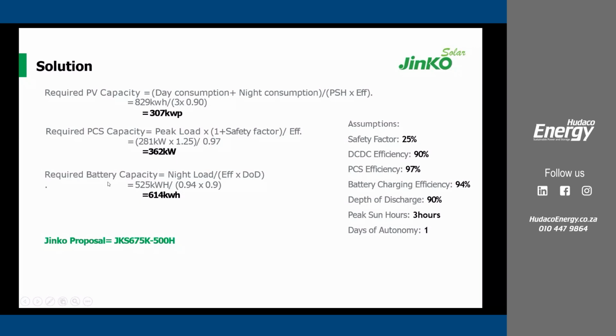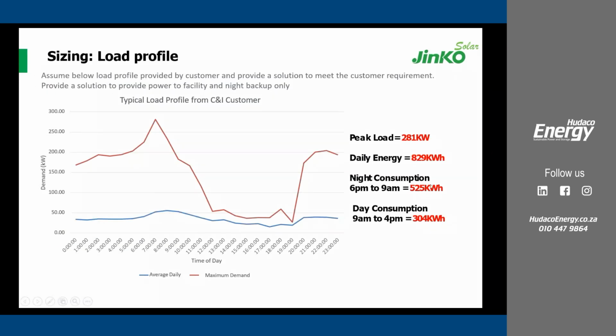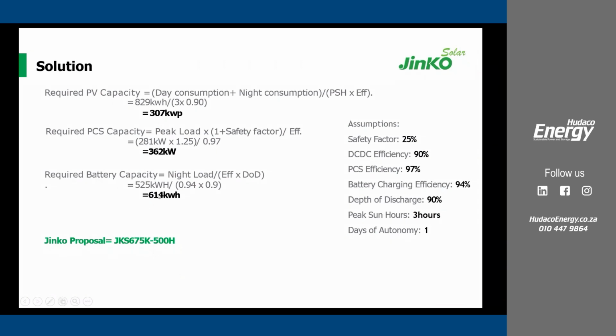Then we also need to size for the batteries. That is knowing the night consumption, then divided by the charging efficiency and also the DOD. The night consumption was 525, and remember, the backup was only for the night. So 525 divided by these two factors makes it 614 kilowatt hours.